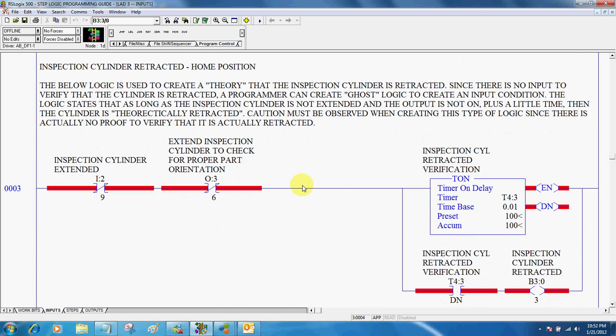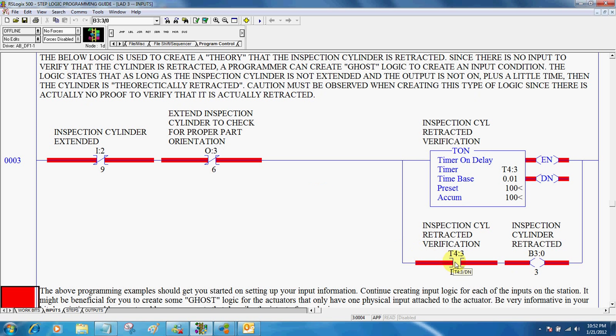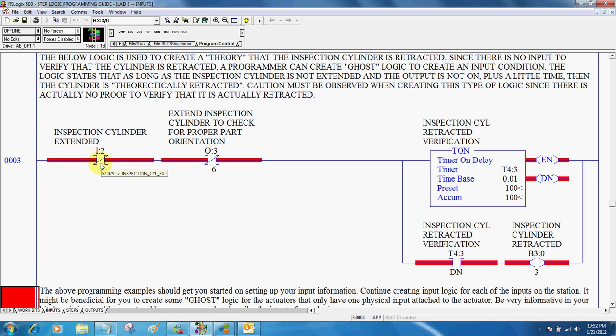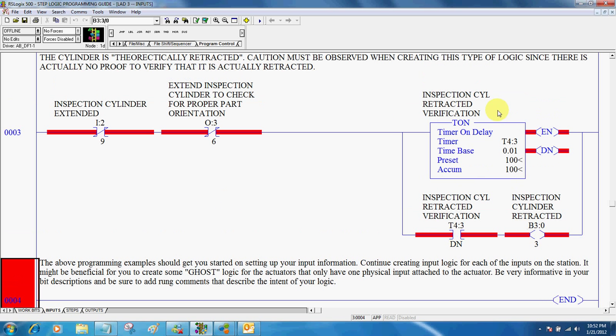One thing that we can do as a programmer is create some ghost logic. Now with the inspection cylinder, there's no way of knowing whether or not it is really retracted. So we can get around that. If we say the inspection cylinder is not extended, and the output to extend it is not on, plus a little bit of time, then chances are the inspection cylinder actually is retracted. That's the best we're ever going to be able to do with that type of situation when we don't have an actual input to tell us that it's retracted.